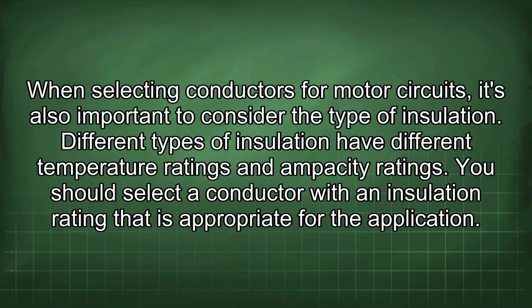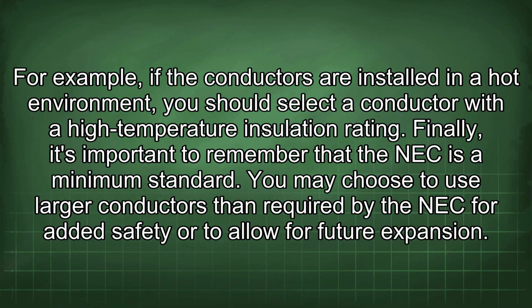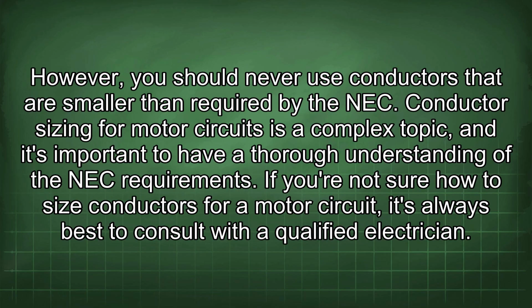ambient temperature. When selecting conductors for motor circuits, it's also important to consider the type of insulation. Different types of insulation have different temperature ratings and ampacity ratings. You should select a conductor with an insulation rating that is appropriate for the application. For example, if the conductors are installed in a hot environment, you should select a conductor with a high temperature insulation rating. Finally, it's important to remember that the NEC is a minimum standard. You may choose to use larger conductors than required by the NEC for added safety or to allow for future expansion. However, you should never use conductors that are smaller than required by the NEC.